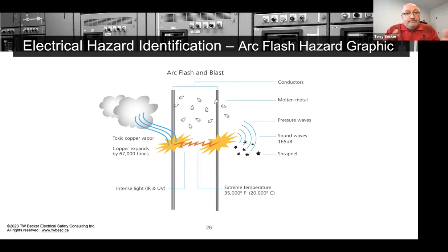Got some videos coming up, and again, we can take a look at some arc flash and what actually occurs. So we have at the point of the arc 35,000 degrees F, 20,000 degrees C. We don't see that. That's not the temperature that the worker is exposed to. It generates incident energy when we have that abnormal arcing fault. So the incident energy is in calories per centimeter squared. And 1.2 calories per centimeter squared is a very important value because that's the energy that could burn exposed skin, right? And or ignite flammable clothing, cotton or cotton poly, 1.2 calories per centimeter squared.